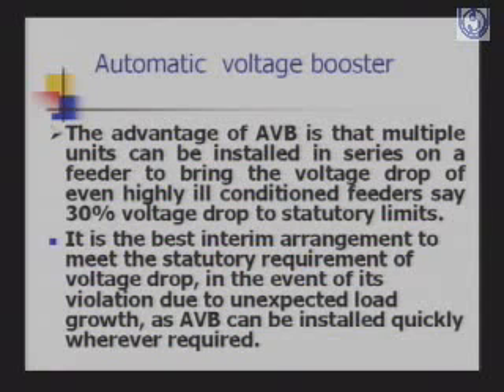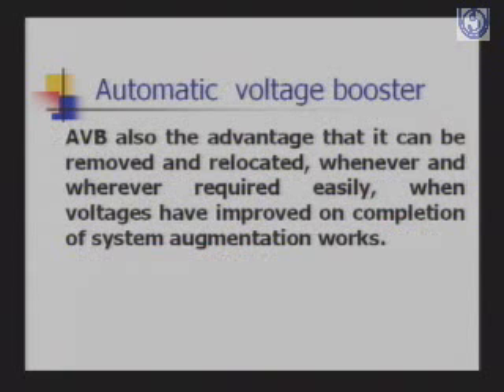It is the best interim arrangement to meet the statutory requirements of voltage drop in the event of violation due to unexpected load growth, as the automatic voltage booster can be installed quickly wherever required, and it can also be shifted easily whenever voltages are improved on completion of system augmentation works. So it is like a voltage booster, a voltage stabilizer, and it can be easily installed and easily removed.